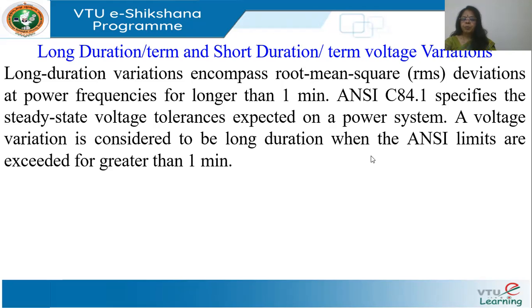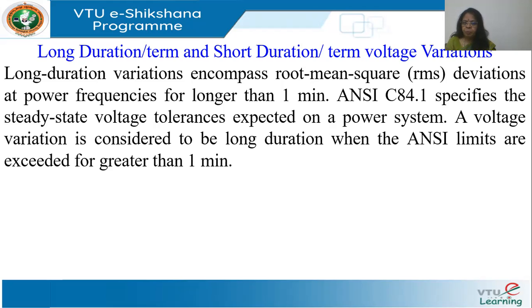The ANSI C84.1 specifies the tolerance we expect from a power system. The utility cannot guarantee a constant voltage all the time because the power system is very dynamic. A utility cannot tell an industry it will supply exactly 66 kV, nor can an end consumer expect exactly 231 volts at 50 Hz all the time.